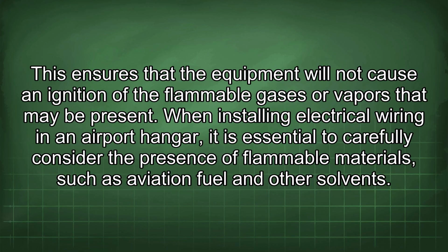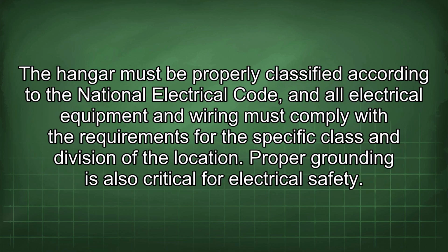This ensures that the equipment will not cause an ignition of the flammable gases or vapors that may be present. When installing electrical wiring in an airport hangar, it is essential to carefully consider the presence of flammable materials such as aviation fuel and other solvents. The hangar must be properly classified according to the National Electrical Code, and all electrical equipment and wiring must comply with the requirements for the specific class and division of the location.